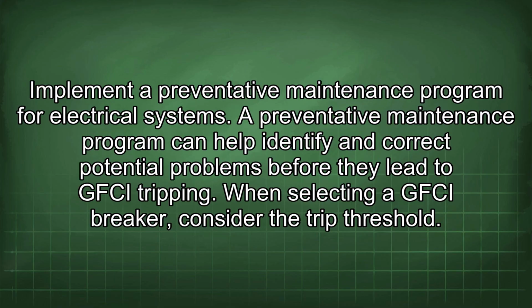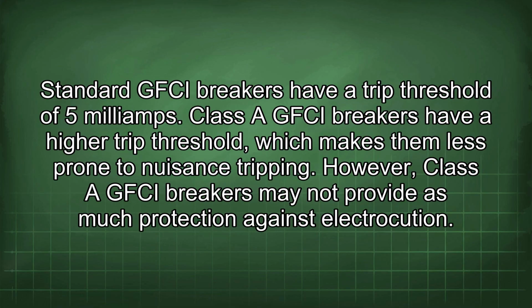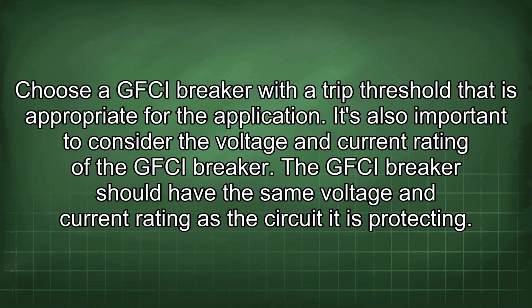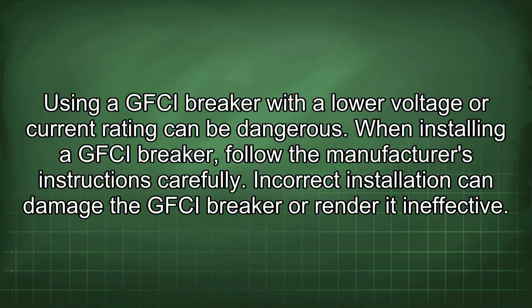When selecting a GFCI breaker, consider the trip threshold. Standard GFCI breakers have a trip threshold of 5 mA. Class A GFCI breakers have a higher trip threshold, which makes them less prone to nuisance tripping. However, Class A GFCI breakers may not provide as much protection against electrocution. Choose a GFCI breaker with a trip threshold that is appropriate for the application. It's also important to consider the voltage and current rating of the GFCI breaker. The GFCI breaker should have the same voltage and current rating as the circuit it is protecting. Using a GFCI breaker with a lower voltage or current rating can be dangerous.